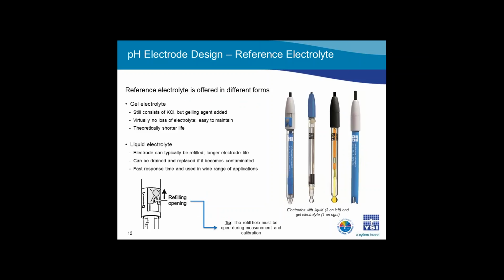Now, the form of KCl can vary. Gel electrolyte still consists of KCl, but a gelling agent is added in order to prevent the electrode from losing electrolyte too quickly. Since they cannot be refilled, electrodes with gel electrolyte are easier to maintain, but they do have a shorter lifetime than those with liquid electrolyte. Field electrodes are typically gel-filled.